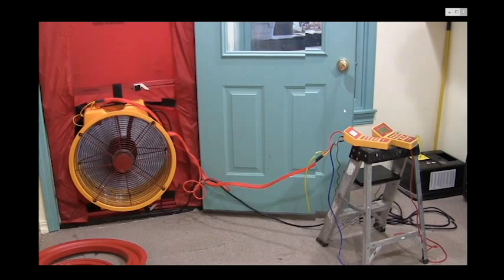And basically what I was doing on this drop soffit was seeing, did they seal on the back side there and avoid creating a thermal bypass, or is the drywall on the front of that soffit really our air barrier?